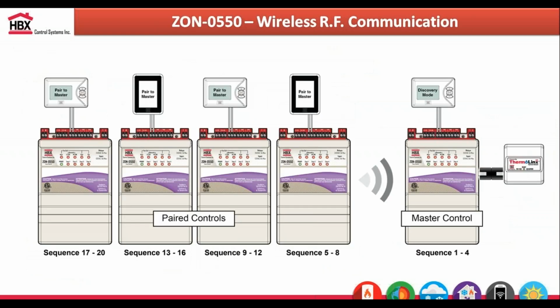In terms of doing more than 4 zones, we also have added wireless communication between zone controllers, so they can actually talk to each other just through radio frequency. Again, it's 2,000 feet open air communication between zone controllers. How you would do this is you put in a master zone controller, so zones 1 to 4 is your master, and zones 5 to 8 would just pair to that master zone controller. How you do this, which we'll talk about in a different webinar on zoning, is all done by the thermostat. The thermostat tells you that it's in discovery mode and that pairing is successful, so it makes it real nice.